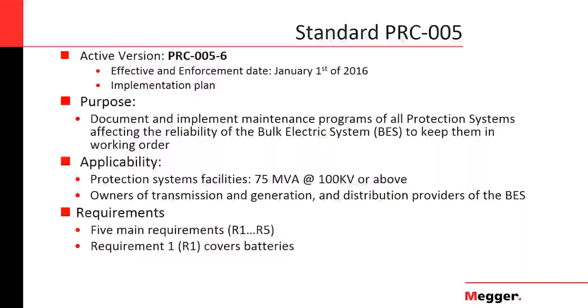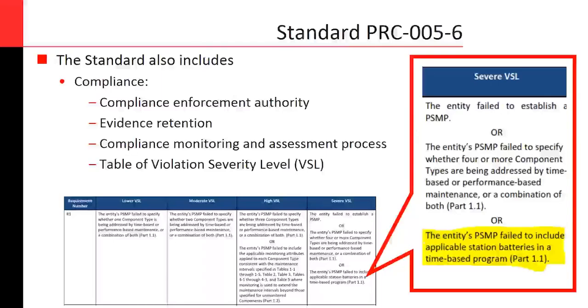Moving on into the details of this standard, there are 5 requirements in the document, called R1 to R5, and the one that covers batteries is R1, just one small part of that requirement. Before getting to the details of that requirement, it is important to mention that the standard also includes a compliance chapter which shows who the enforcement authority is, how you need to keep evidence of the testing and organize that information, and how the compliance monitoring assessment process will be. It also has this table of violation severity levels, which I was mentioning in a previous slide.